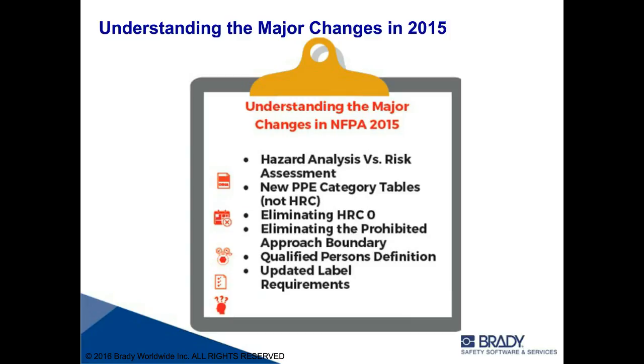Everyone's familiar with the HRC, hazard risk categories, which is what used to be in 70E as the table method. People could look at the different categories, 0 through 4, and say, I have my Cat 1 PPE, I have my Cat 2. The tables have been completely rearranged, and now there are two sets. The first table is task-oriented, and looks at various tasks and says whether or not you need to wear PPE. Once you've established that, you go to the second set of tables that defines your PPE category, whether that's 1 through 4.